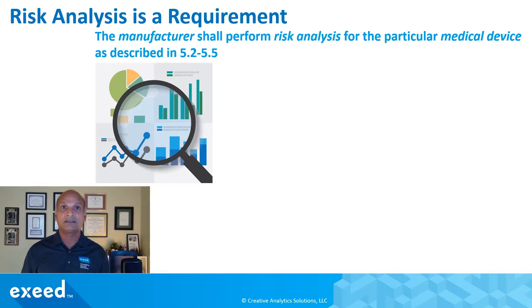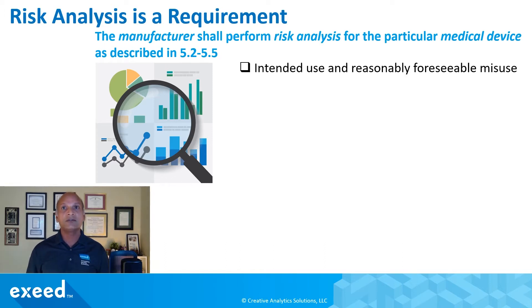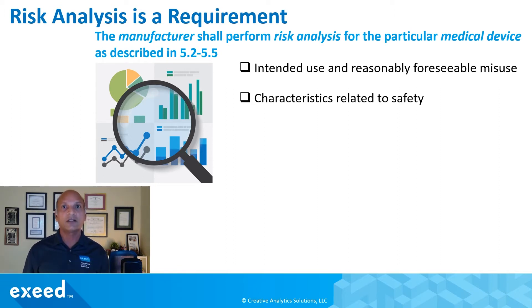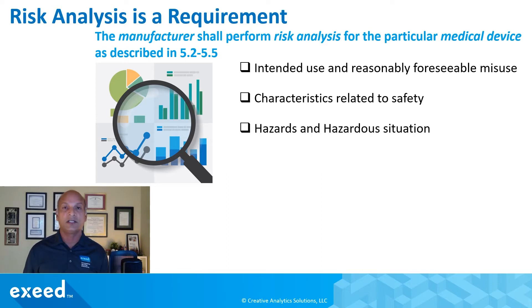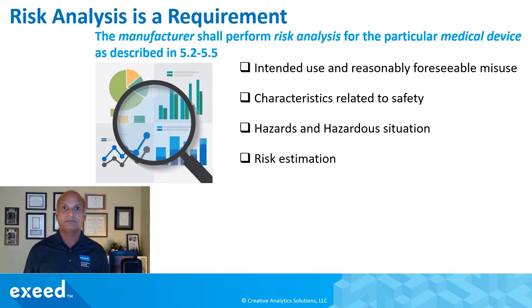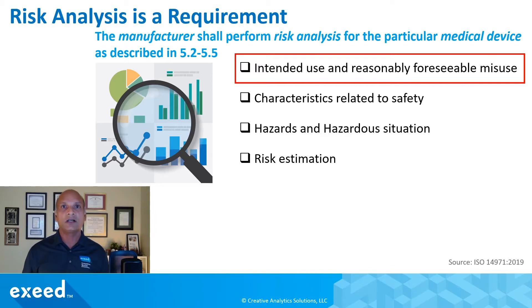Risk analysis is a requirement as described in clauses 5.2 through 5.5 in ISO 14971, and it starts with intended use and reasonably foreseeable misuse — that's the context for the risk analysis. Then you have to talk about characteristics related to safety, then look at hazards, hazardous situations, and harms, as we discussed using a PHA. And then you have to estimate the risk. Today we're going to focus on intended use and reasonably foreseeable misuse.